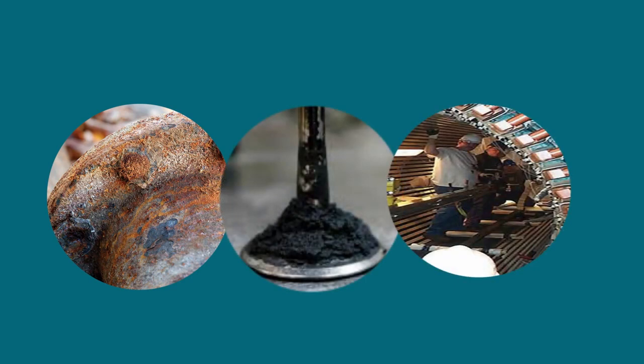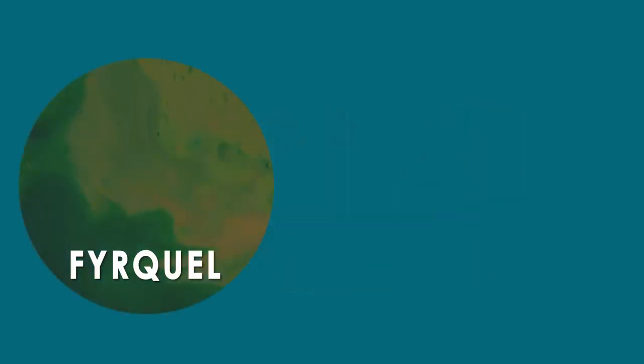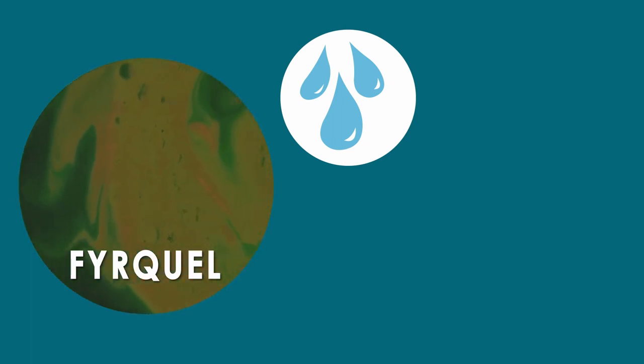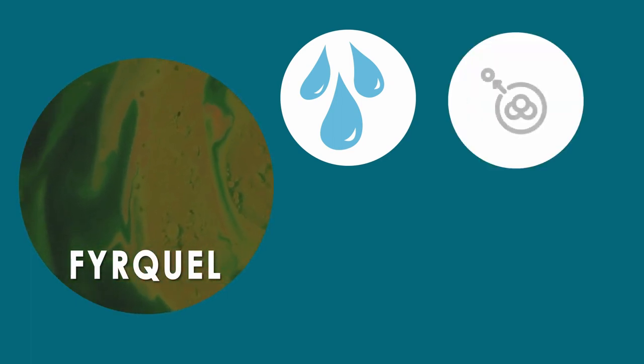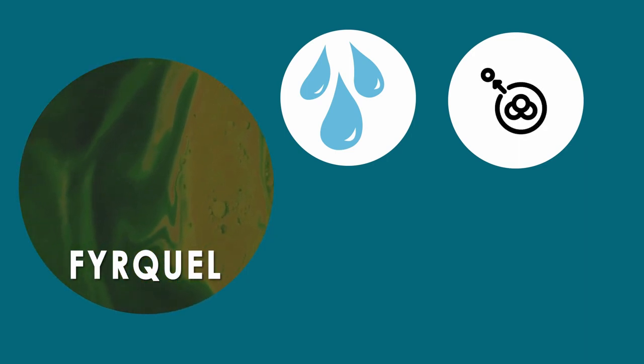The most common problems encountered by Fyrquel fire-resistant hydraulic fluid while in use include hydration, which triggers the decomposition of phosphoric acid esters with formation of alcohols and acids, and oxidation, which, along with high temperature, contributes to decomposition of Fyrquel fluid.